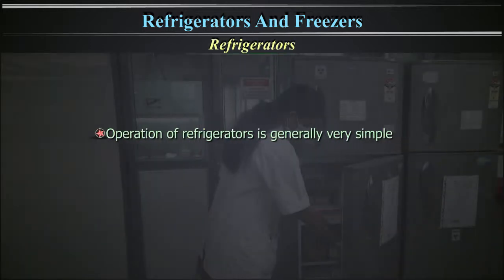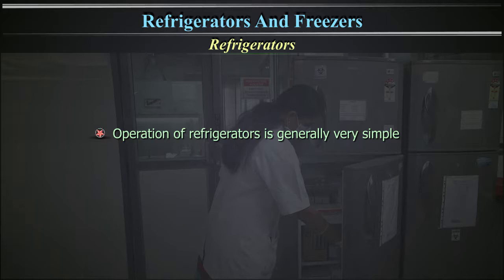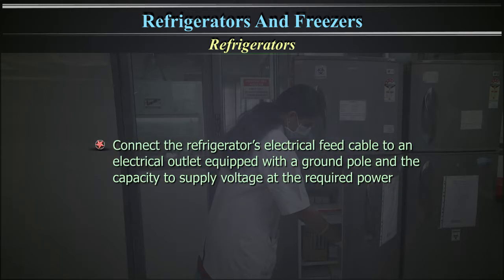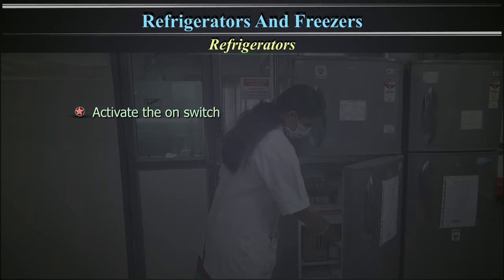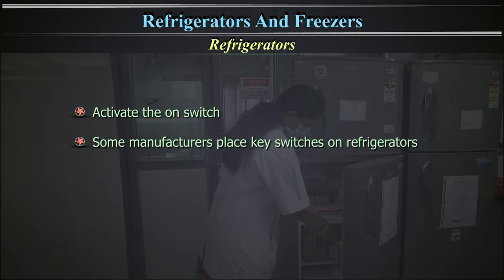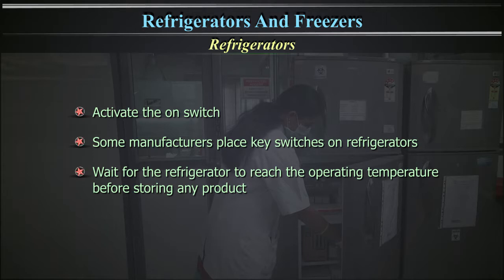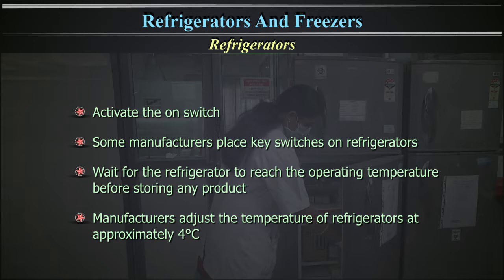The operation of refrigerators is generally very simple, and each manufacturer gives basic recommendations. 1. Connect the refrigerator's electrical feed cable to an electrical outlet equipped with a ground pole and the capacity to supply voltage at the required power. 2. Activate the on switch. Some manufacturers place key switches on refrigerators. Wait for the refrigerator to reach the operating temperature before storing any product. Manufacturers adjust the temperature of refrigerators at approximately 4 degrees Celsius.